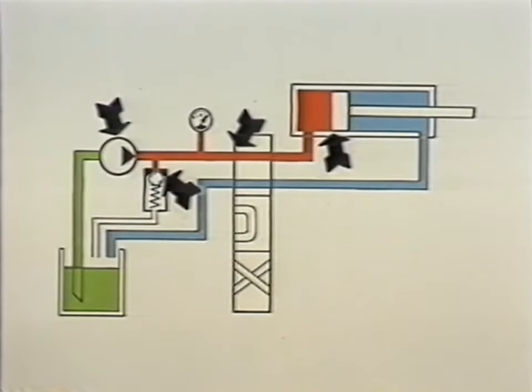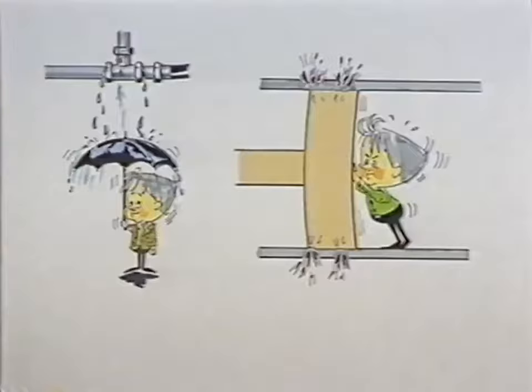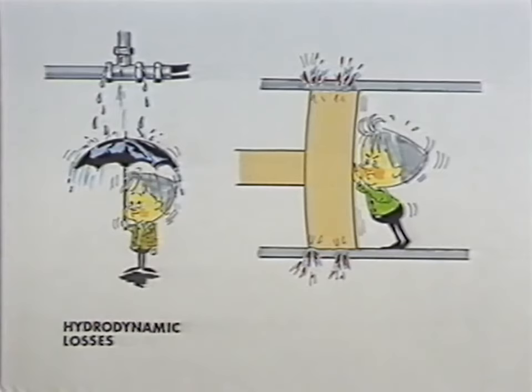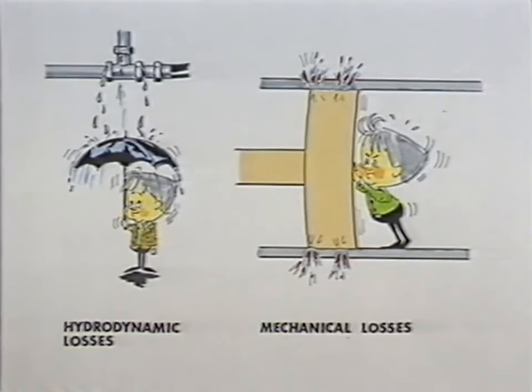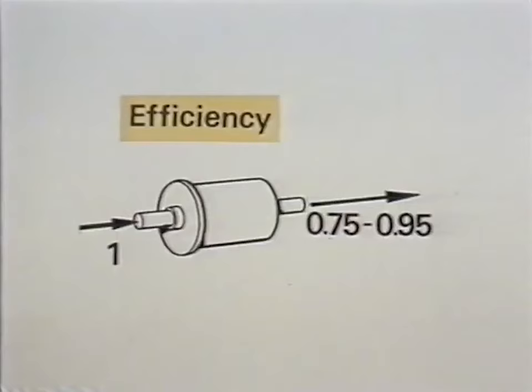Also, some of the capacity is lost through friction between different components inside the pump. Leakage and flow losses are known under the common name of hydrodynamic losses because fluids are involved. Losses caused through friction are termed mechanical losses.